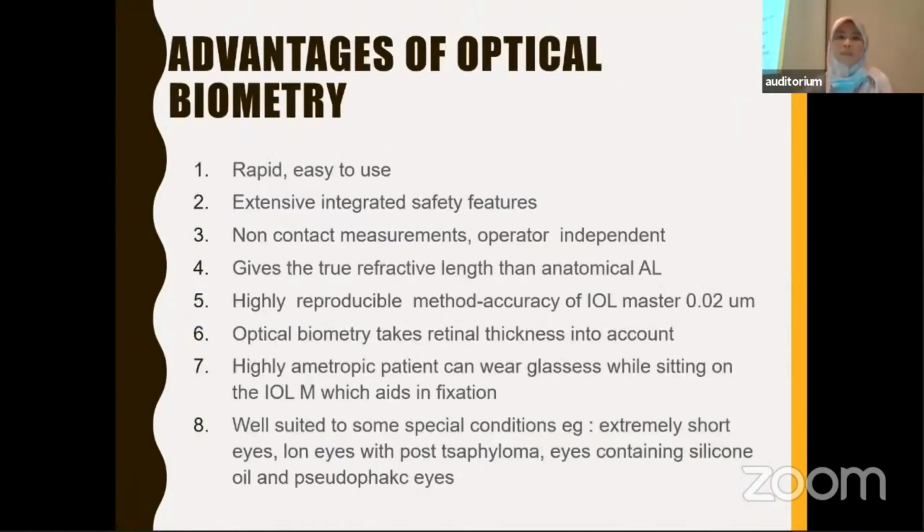Advantages of optical biometry: rapid and easy, extensive integrated safety features, non-contact measurement, and operator independent. It gives the true refractive length rather than anatomical axial length, and is a highly reproducible method; the accuracy of the IOL Master is 0.02 micrometer.